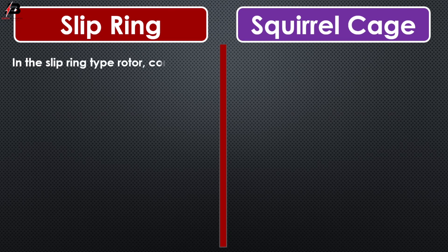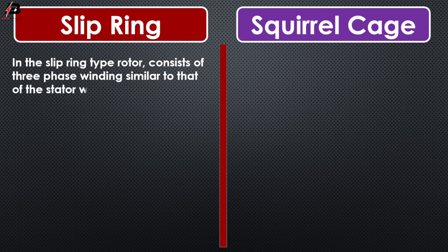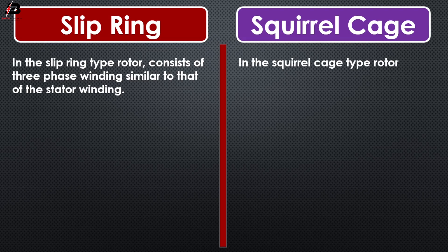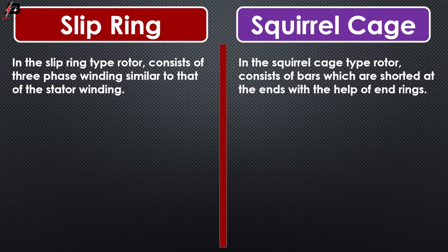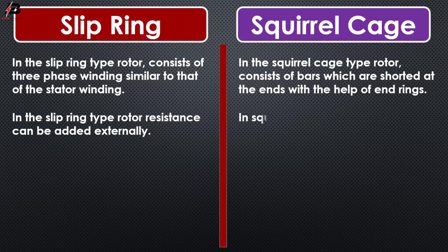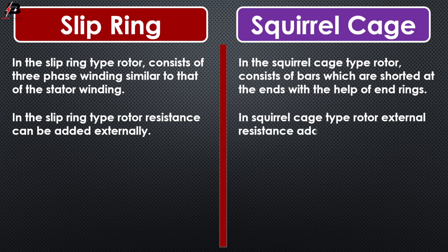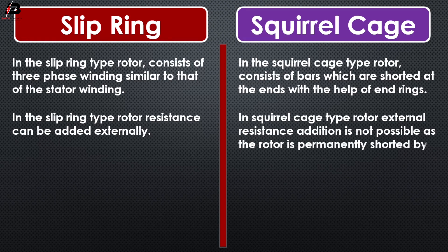Some simple differences between slip ring and squirrel cage rotor: in the slip ring type rotor, it consists of three-phase winding similar to that of the stator winding. In the squirrel cage type, the rotor consists of bars which are shorted at the end with the help of end rings. In slip ring type, resistance can be added externally; in squirrel cage type, external resistance addition is not possible as the rotor is permanently shorted by the end ring.